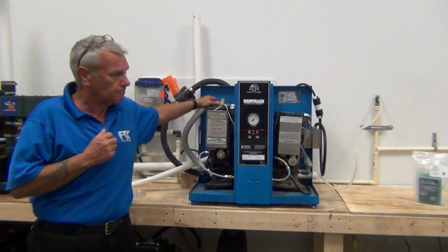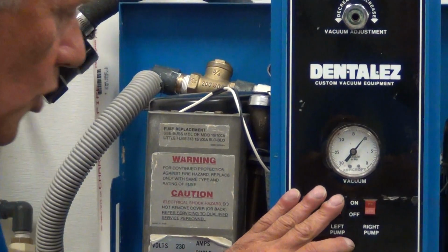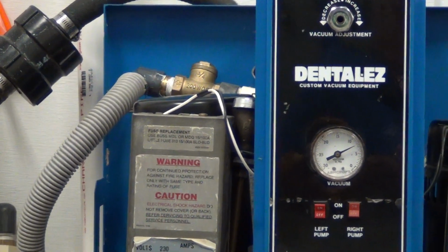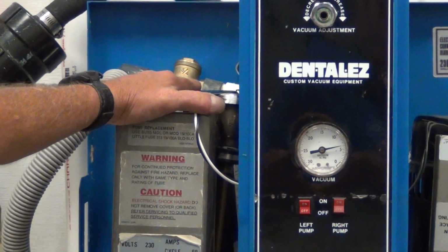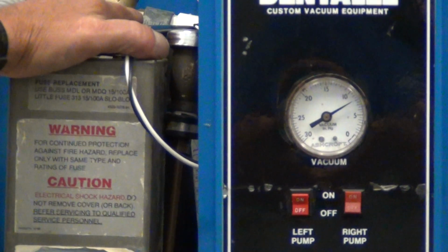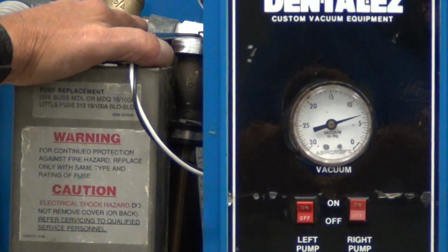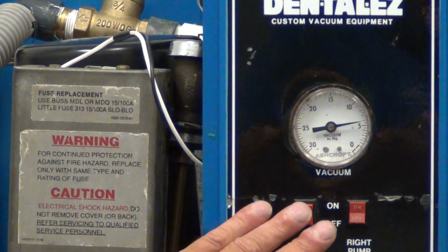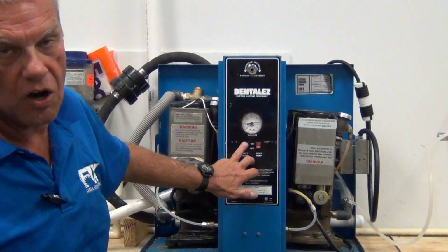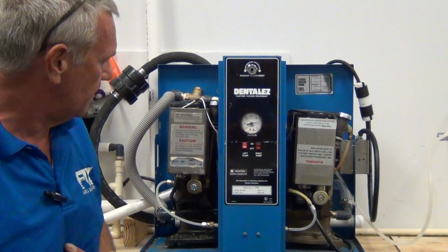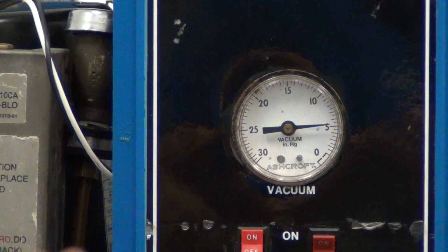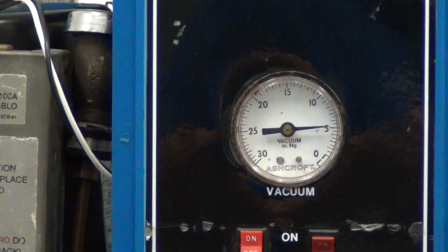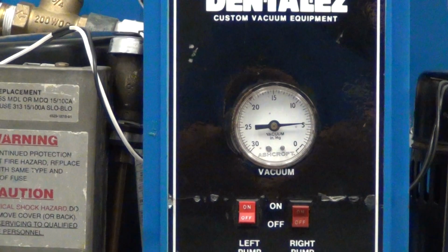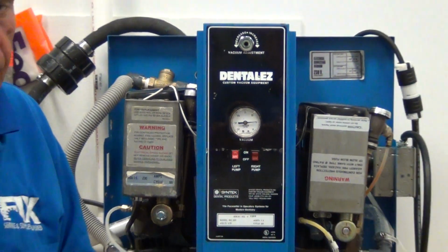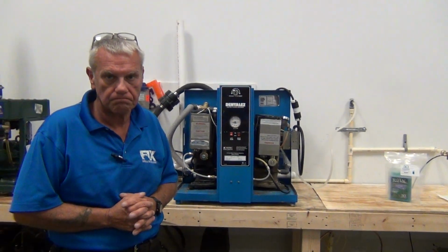Our check valves. To check our check valves, I'm going to turn one motor off. In this case, we have turned off the left motor. We're maintaining 8 inches of mercury. We've jumped back up to alternating between 8 and 10 inches of mercury, which is perfectly acceptable. Next, we're going to turn on the left-hand pump again and turn off the right-hand pump and check our inches of mercury on the left-hand pump. The left-hand pump is slightly weaker than the right-hand pump according to the gauge. Don't let that worry you. You will never find a pump that both pump heads are perfectly equilibrated. They're all going to be a couple inches of mercury variation.